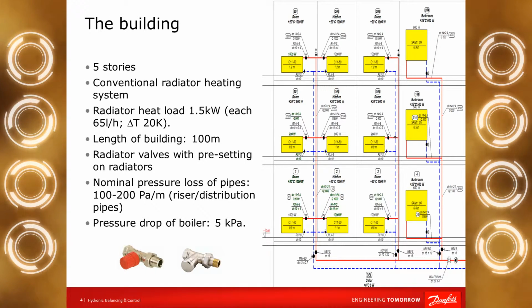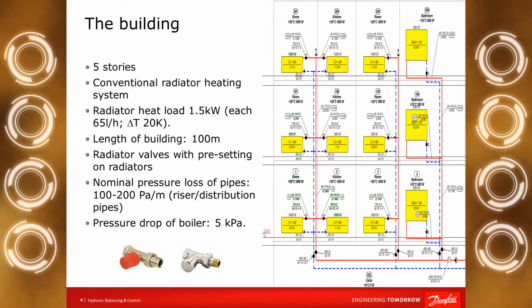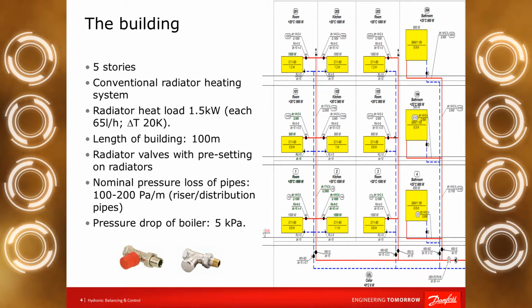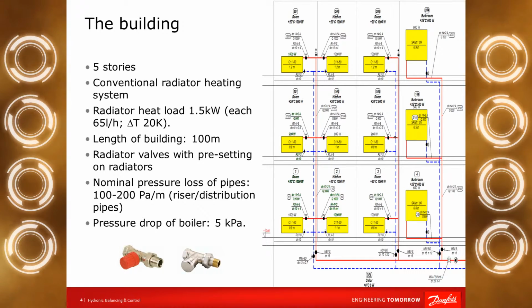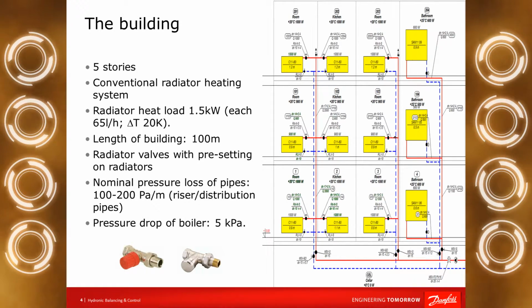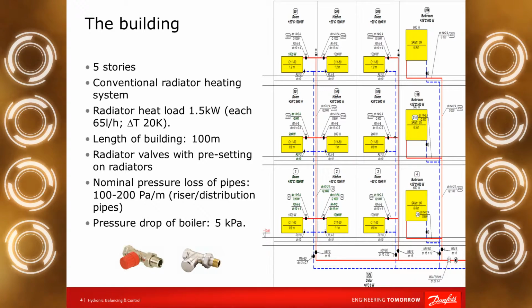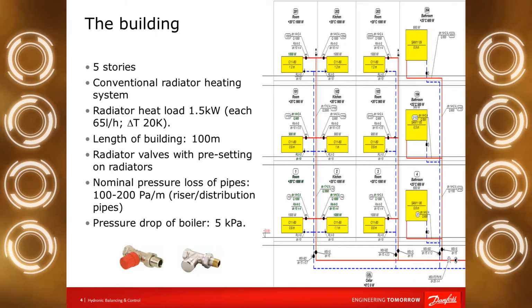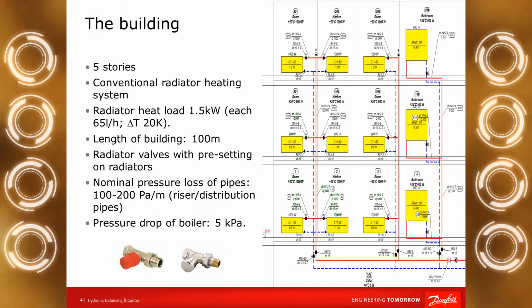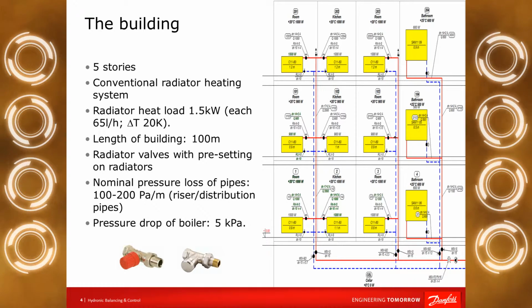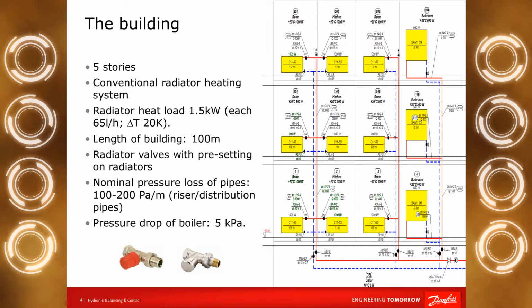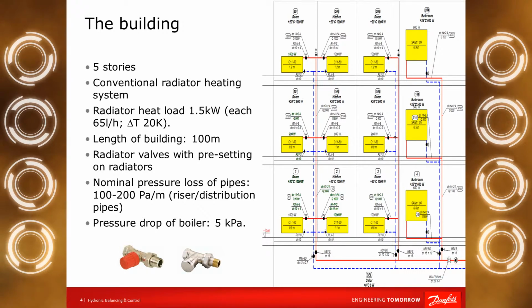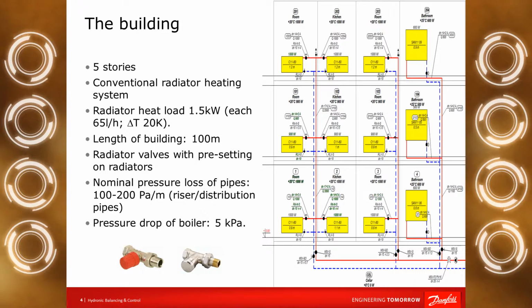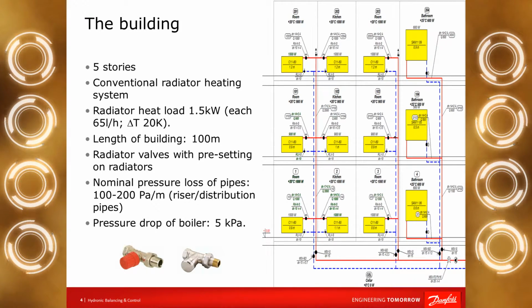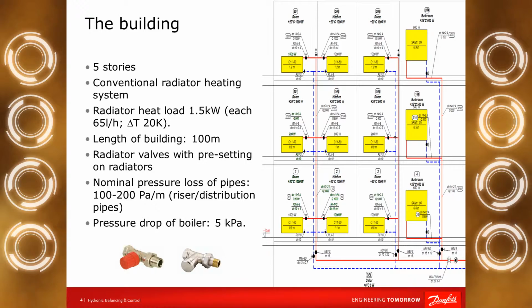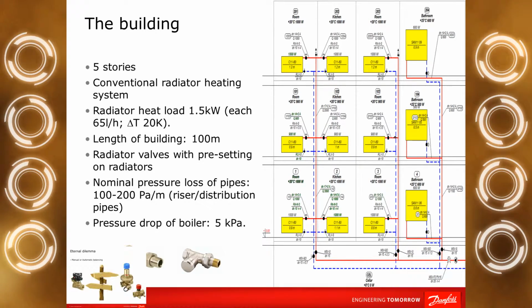Very important: how do we design the system? In my calculation, I used 100-200 Pascal per meter nominal pressure drop for pipe sizing, which strongly affects the overflow phenomenon. In our case, I used a 5 kilopascal pressure drop on the heat source. It can be a boiler or a heat exchanger. Normally, the pressure drop on heat exchangers in a district heating substation is more than 5 kilopascal, but I tried to calculate on the safe side to show you realistic figures.